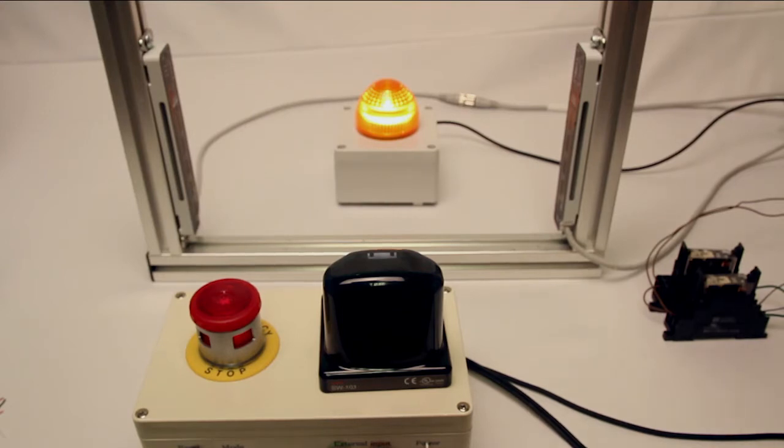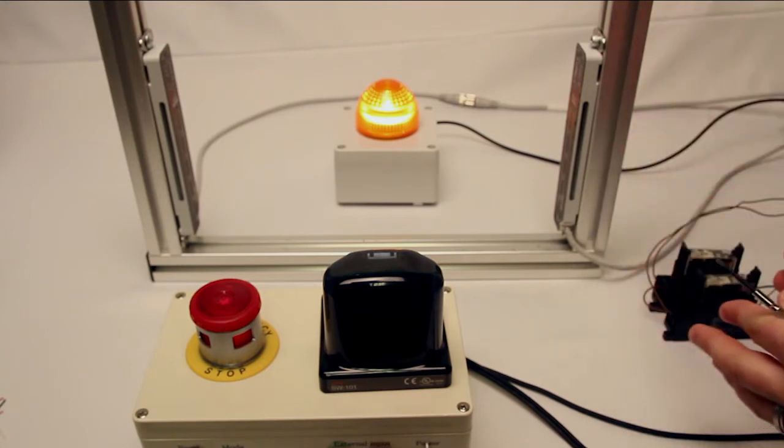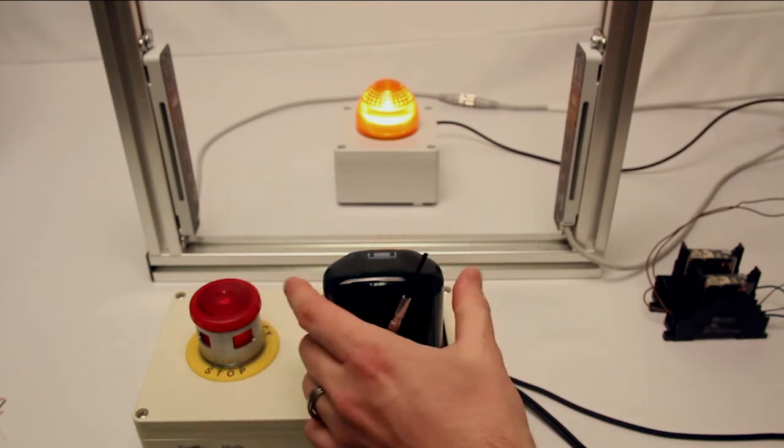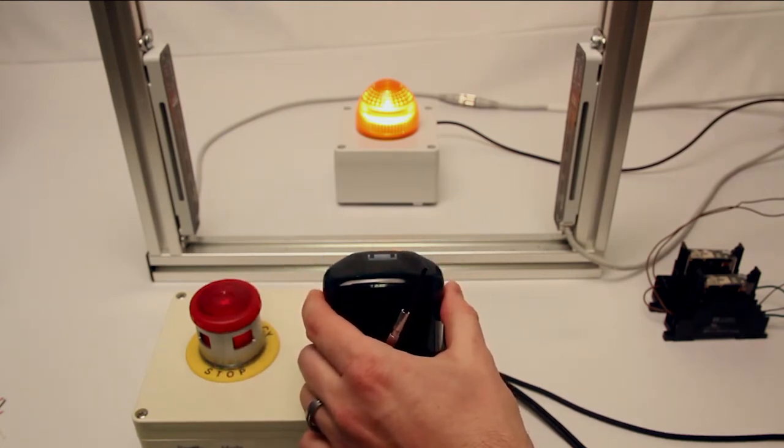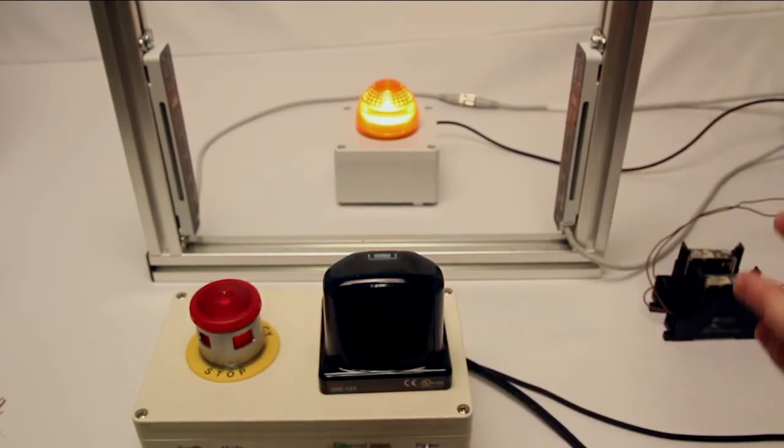So what this actually does is it's going to take all of your safety peripherals and monitor them using just the light curtain itself. On a typical machine, you may have more than just a light curtain. Maybe you have a door switch or an e-stop switch, or in this case, one of our SW101 touch switches. All of these are going to be fed into the light curtain so that you don't need an extra controller.